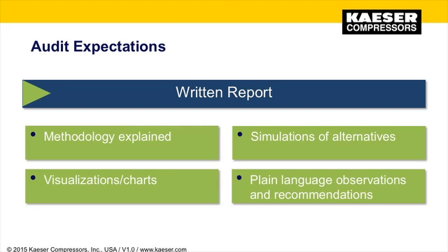With this data, simulations can be created with alternative mixes of compressors, whether it be existing or new, or a combination of both. This will accurately project system performance after any changes are made. This can enable you to identify the equipment solution that will offer the best balance of stable pressure, reliability, and low energy consumption. There will typically be a clear winner when it comes to specific performance or efficiency. However, whether these changes have any acceptable ROI would need to be qualified. These reports should be written to facilitate decision making.